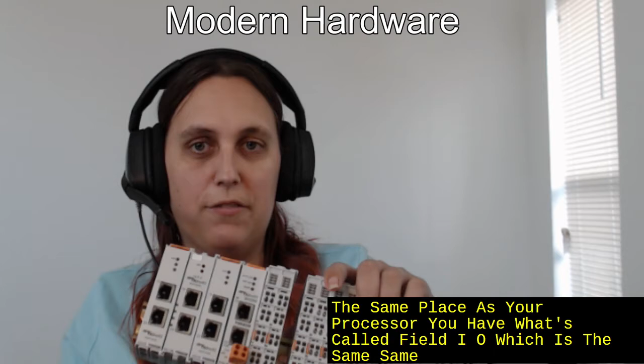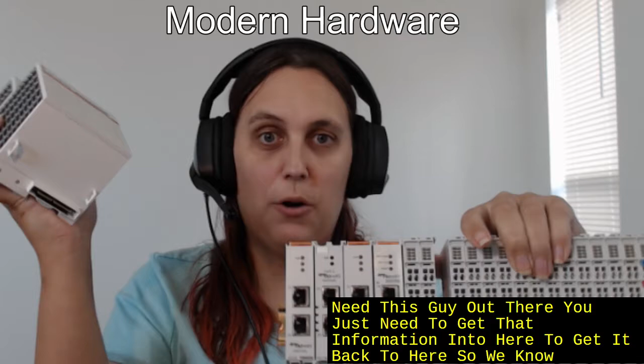You have what's called field IO, which is the same stuff, it just lives where your field devices live. For instance, on Test Track, the car goes outside and makes that big loop around the bank. You have safety sensors all over the place out there to keep track of the cars—where they are, how far apart, how fast they're going. You don't need the PLC itself out there; you just need to get that information back here so we know what's going on. So field IO lives out there on the big bank, keeping track of everything and sending that information back to the computer room where there's a whole bunch of these doing their job.